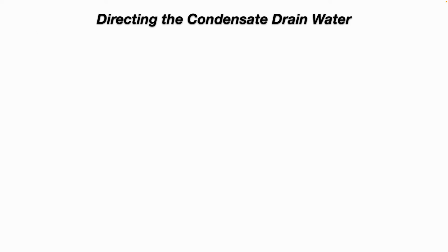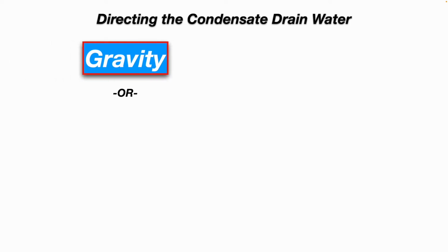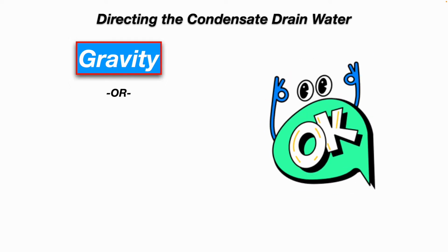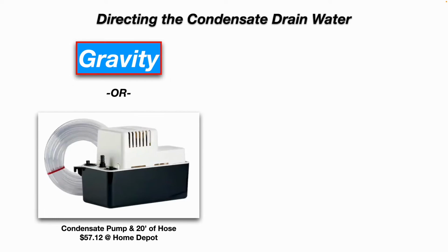Directing the condensate drain water. So your first option, the easiest, is gravity drain. As the condensate comes out of that drain tube, you would simply direct it into a 5-gallon bucket or a 55-gallon drum. Obviously, you would need to make sure that you elevate your dehumidifier high enough to allow that to occur. Or you can buy one of these condensate pumps.